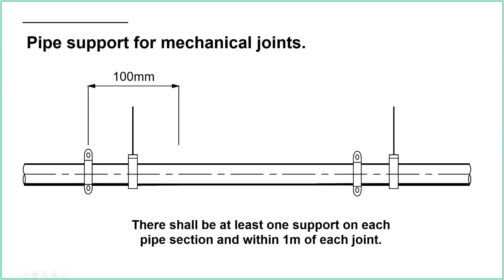And then pipe supports from mechanical joints. So this is an important one. Whenever we are connecting 2 bits of pipe together, so where we have a mechanical or a grooved coupling, or we are changing direction, or we're screwing one piece of pipe into another, then we're going to need a support within 1 meter of each joint. Okay, so within 1 meter of each joint, we need a support. Another mistake there, isn't there? It says 100 millimeters, so it should be 1,000 or 1 meter.